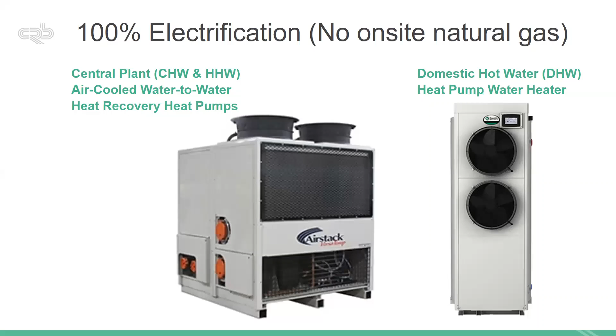The beauty of this is, run in chiller mode, it's roughly the efficiency of an air-cooled chiller. Run in heater mode, it's roughly the same. But run simultaneously, we're actually getting COPs exceeding 8. To put that in perspective, a chiller might be 3, 4, 5. So to get a COP of 8 is wonderful. For those who don't talk in COP very often - coefficient of performance - a boiler might be 85-90% efficient, which is a COP of 0.85 or 0.9. Electric resistance is nominally 100% efficient, so that's a COP of 1. We're not just 3, not 4, not 5 - we're 8. It's really exciting, and that's why this technology is starting to prove it has a future.